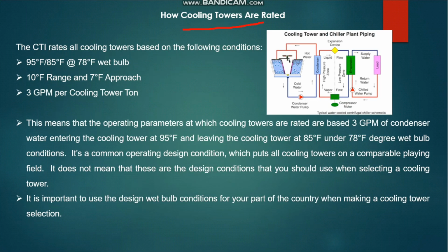How are cooling towers rated? That is the important thing. The Cooling Technology Institute rates all cooling towers based on the following condition: 95 degrees Fahrenheit and 85 degrees. That means 95 degrees is the entering water temperature and 85 degrees is the leaving water temperature, at 78 degrees Fahrenheit wet bulb temperature. This is not dry bulb, this is the wet bulb temperature. And 10 degrees Fahrenheit range and 7 degrees Fahrenheit approach. These two I will explain now.